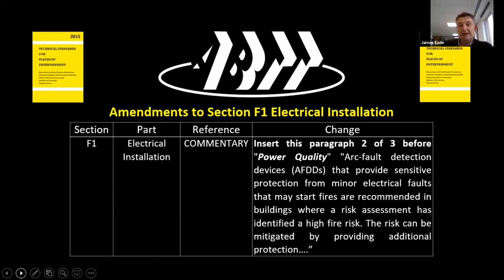Then the proposal in Amendment 2, which went out for public comment earlier this year and is now being worked through, introduced a very similar requirement to that for RCDs, that any circuit under 32 amps should have an AFDD on it. That garnered a lot of comments, as you can imagine, in the draft for public comment process. It's currently being worked through, and the jury's still a bit out on what form the new wording is going to take.